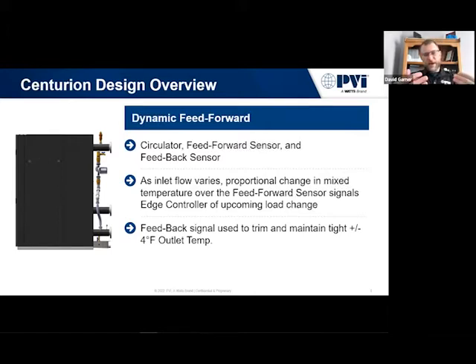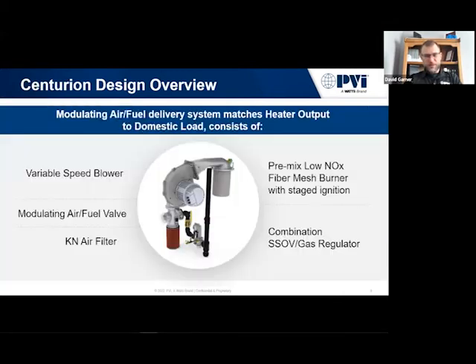From there, we can actually modulate, and with that 20-to-1 turn down, we can just pretty much dial in exactly what firing rate we need to maintain temperature, and that gives us that extremely tight plus or minus 4 degree set point on our discharge temperature.